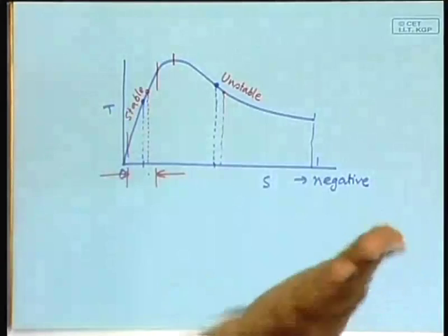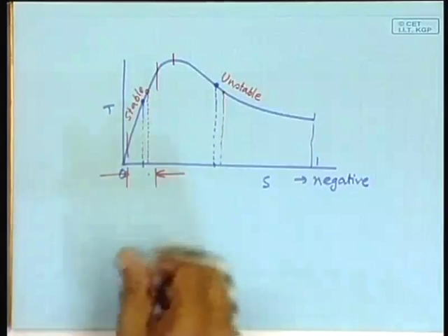But still, at present time, I am talking about 2007, India has about 3000 megawatts of wind electrical generation capacity. It is a large amount, and almost all of them are simple squirrel cage induction generators connected to the grid, which means they effectively have no variation of the speed really, and that is actually maintained by variation of the pitch angle. Why? Because this is cheap. The squirrel cage induction generator is very inexpensive. So, if you are buying on the basis of the lowest quotation, obviously this wins, because this is cheap and very rugged, nothing really happens.